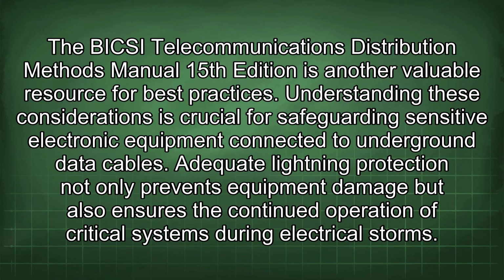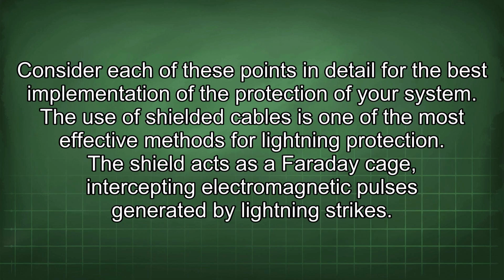Adequate lightning protection not only prevents equipment damage but also ensures the continued operation of critical systems during electrical storms. Consider each of these points in detail for the best implementation of the protection of your system. The use of shielded cables is one of the most effective methods for lightning protection. The shield acts as a Faraday cage, intercepting electromagnetic pulses generated by lightning strikes.